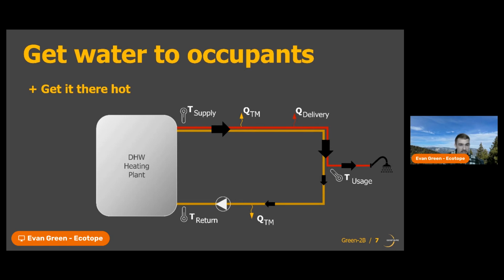So as this hot water is traveling to the fixture, it's going to cool the entire time it's going through this pipe, because the water is at about 120 degrees and our environment's a lot cooler. So naturally, we're going to have that heat loss no matter what we do. So in order to counteract this cooling of the water as it goes to the fixture, we're going to need to bump up the temperature that's leaving the heating plant. If we need 115 degrees at the fixture, we might need to serve it from the heating plant at 120. So it has that, so we can account for that heat loss as it travels to the fixture.